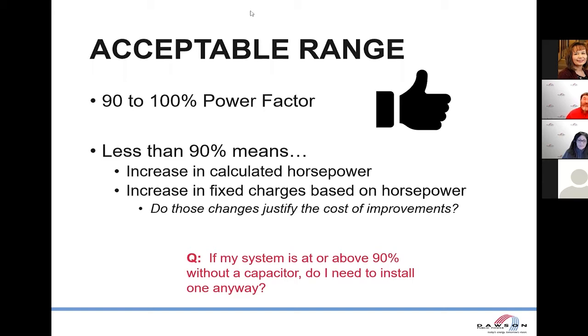So what happens if you're less than 90, right? If you're more than 90, nothing happens. That's acceptable. If you're less than 90, we're going to increase the calculated horsepower on your power bill, and we're going to increase it in fixed charges based on that calculated horsepower. You're going to have to decide for yourself if the changes it would take to fix this power factor justify the cost of the improvements, right?